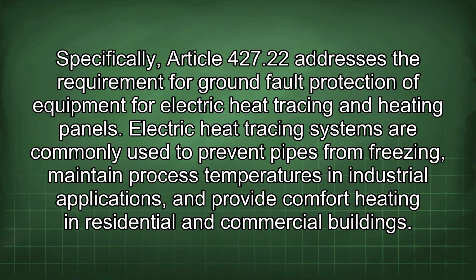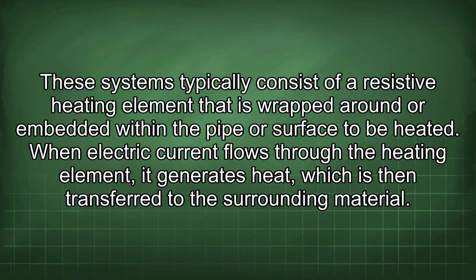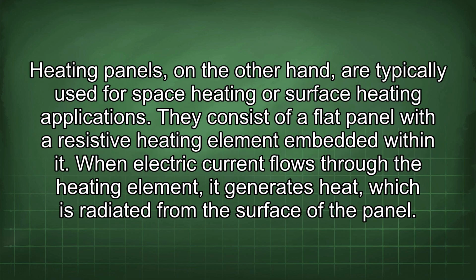Electric heat tracing systems are commonly used to prevent pipes from freezing, maintain process temperatures in industrial applications, and provide comfort heating in residential and commercial buildings. These systems typically consist of a resistive heating element that is wrapped around or embedded within the pipe or surface to be heated. When electric current flows through the heating element, it generates heat, which is then transferred to the surrounding material. Heating panels, on the other hand, are typically used for space heating or surface heating applications. They consist of a flat panel with a resistive heating element embedded within it. When electric current flows through the heating element, it generates heat, which is radiated from the surface of the panel.